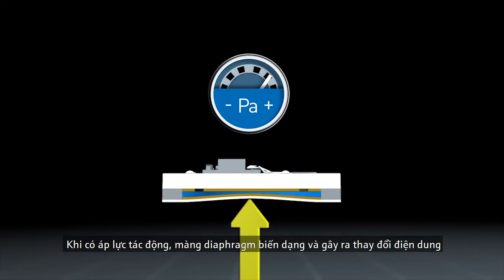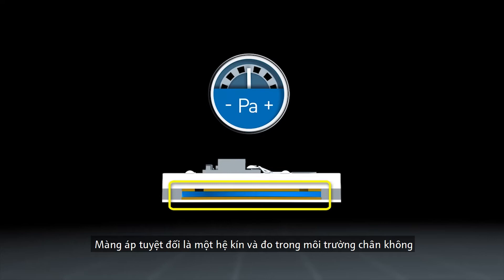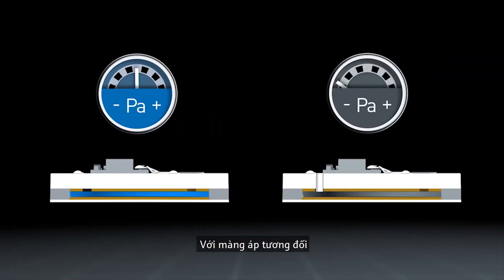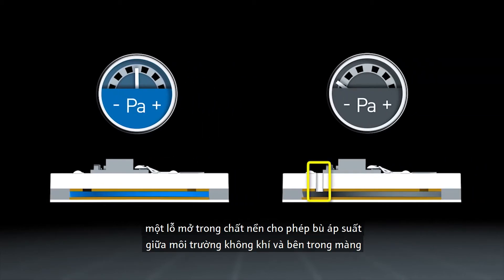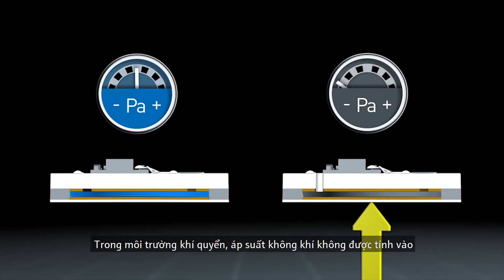As pressure is applied, the diaphragm deforms and causes a change in capacitance. The absolute pressure cell is a closed system and measures against the vacuum. In an atmospheric environment, the air pressure is indicated. In a gauge pressure cell, an opening in the substrate permits the pressure compensation between the atmospheric environment and the inside of the cell. The cell measures values which are relative to the ambient pressure. In an atmospheric environment, the air pressure is not indicated.